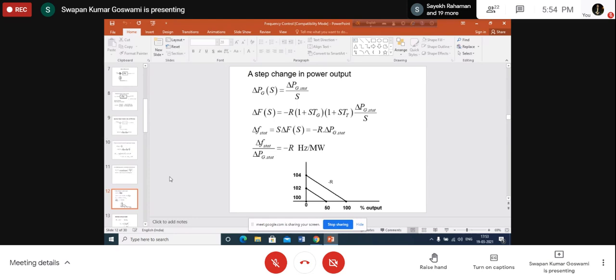So basically, this represents the characteristics of the speed governing system. It has a drooping characteristic because of this expression here, it is minus R, and if you plot, we are given some representative value here. That means if R is 4%, then from no load to full load, the variation in frequency will be 4%, like this. Okay, is it clear?